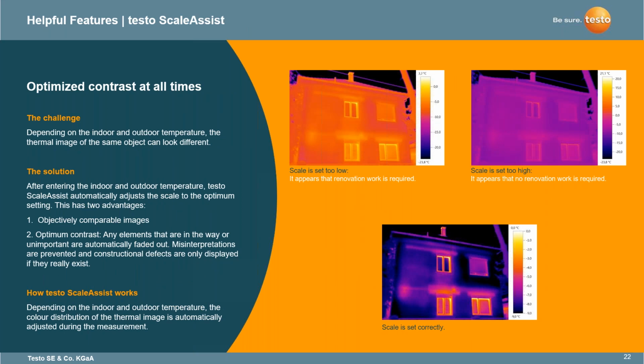The Testo Scale Assist provides optimized contrast at all times. This depends on the indoor and outdoor temperature, since the thermal image of the same object can look different. We have two examples if the scale is set too low or too high. The one aspect thermal imagers generally work off of is the rule of a 10 to 15 to 18 degree difference, that's where you're able to detect.